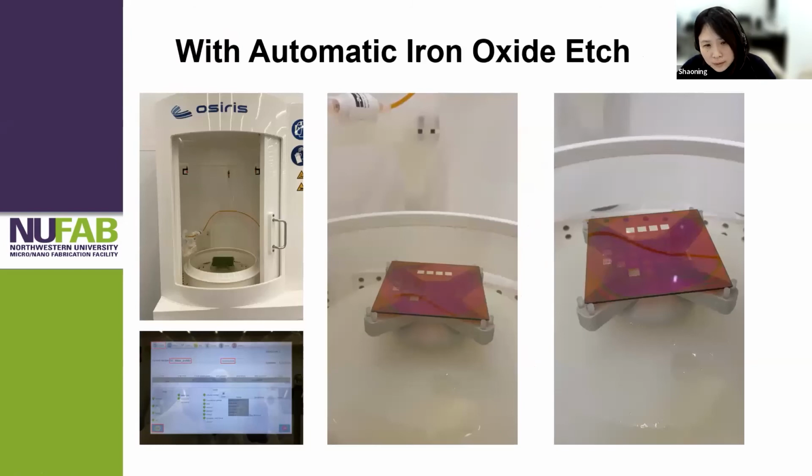So by bringing in this automatic acid etcher, this is a close-up picture of the chamber you're working with. Because currently we have the process ready for the photo mask, users, you don't even have to choose the track, the holder for your sample. Our staff will help you put in the size you need before you start using. What you need to do is come and open the door, put your mask on the holder, just loosely put it there. No other step, close the door.